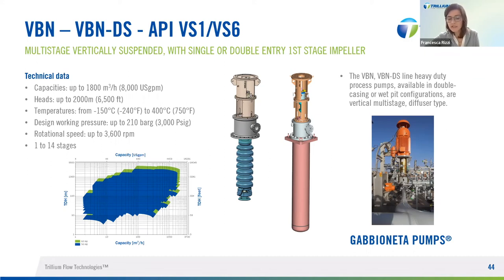Large single suction or double suction first stage impellers allow meeting low NPSH requirements. In addition, assemblies of flow-way bowls and columns and a fabricated discharge head allow meeting more flow and head conditions. So the pumps involved in LNG are many and various, and Trillium's installed base fully reflects this condition.